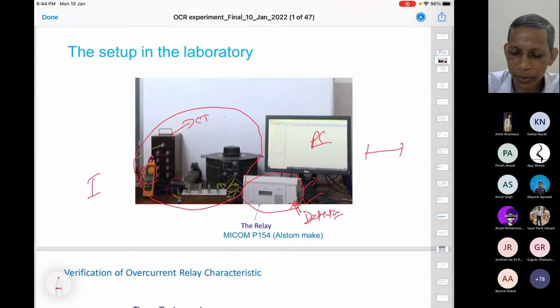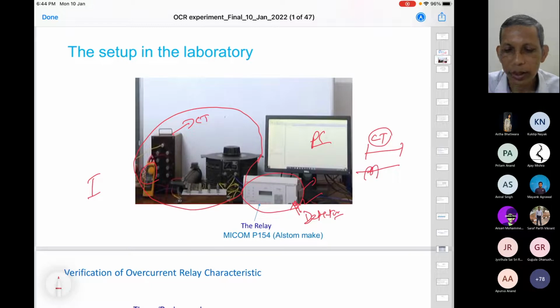So what is done is that, to downscale the current, we put in a current transformer. This current transformer is typically a single turn on the primary, and multiple turns on the secondary side, so that the current becomes substantially low, and that low current becomes the input to the relay. But these relays contain a microprocessor or microcontroller, so the input to them can be only voltage. So the corresponding current has to be converted to voltage. But that is internal to the relay. The relay does that. Agree?